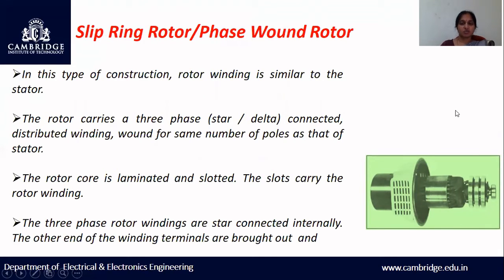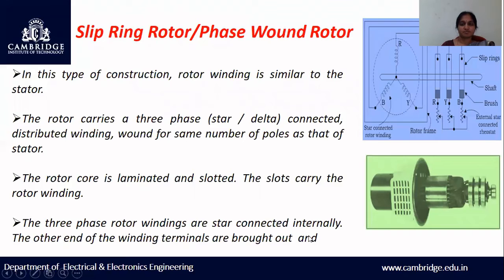The second type is the slip ring rotor or phase wound rotor. In this construction, the rotor winding is similar to the stator. The rotor carries a three-phase star or delta connected distributed winding, wound for the same number of poles as the stator. The rotor core is laminated and slotted, and the slots carry the rotor winding. The three-phase rotor windings are star connected internally, and the other ends of the winding terminals are brought out. As seen in the diagram, additional external resistance can be added, giving you the option to control rotor resistance.